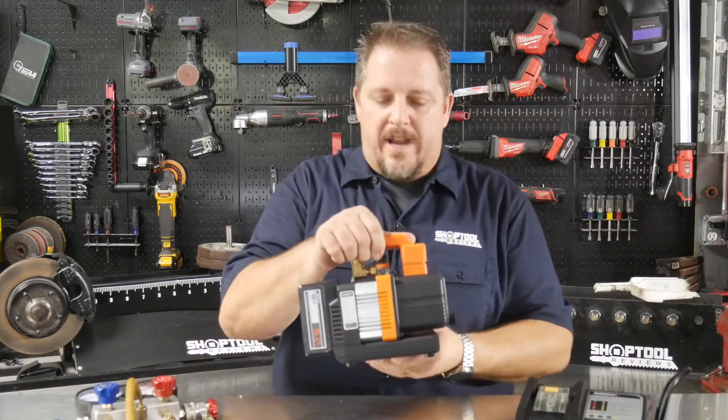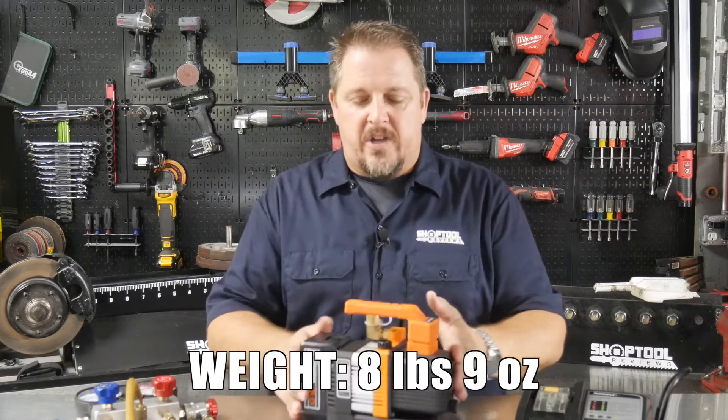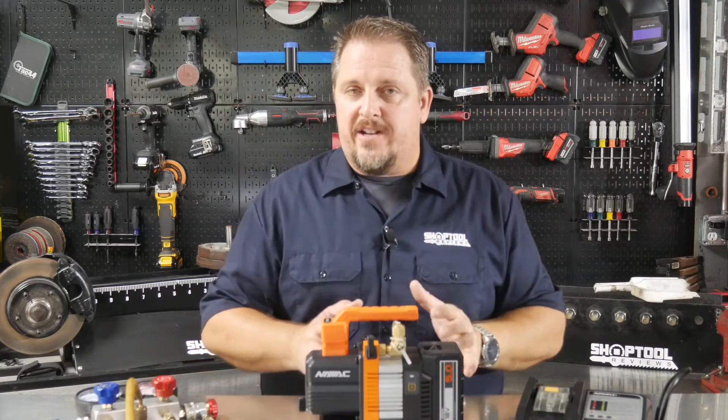The NAVAC actually pulls down to 23 microns, and this thing is not only compact but it's beefy — it's got some weight to it. It's about 8 pounds 9 ounces with the battery on it, so it doesn't feel like a little toy. It's a nice compact unit that should last.